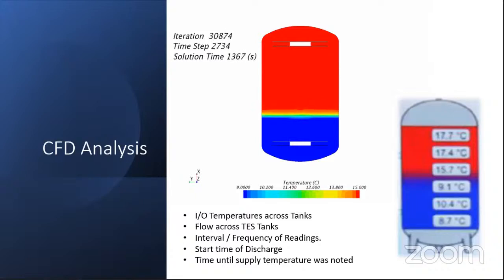Or rather, let us talk in terms of percentages. In a small tank, your thermocline could be covering 20% of the height or 15% of the height sometimes. But in a very large tank, your thermocline could be covering only 5% of the body. So it is largely volume versus flow dependent. And yes, when there are two different temperatures and flow happening within the same tank, thermocline will occur.